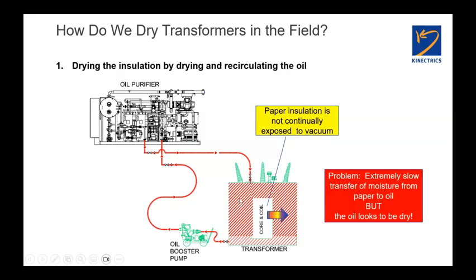But those are going to show that the unit is dry when it is not, because we're not looking at the moisture content of the paper. They're only looking at the moisture content of the oil. And the problem with this methodology, again, is that to dry cellulose, you need to simultaneously apply heat and vacuum. You need those two gradients. In this particular case, because we have not taken the oil out of the unit, the paper is not exposed at all to vacuum. It's covered with oil. So it's not very effective.